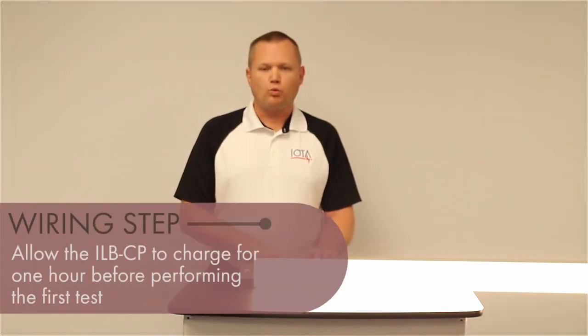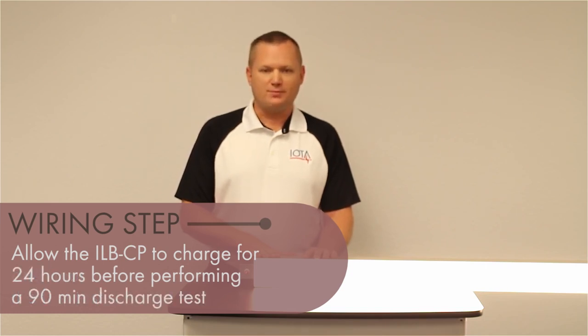Please allow one hour charge time before performing the initial test and an additional 24 hours charge time before performing a full 90 minute discharge.